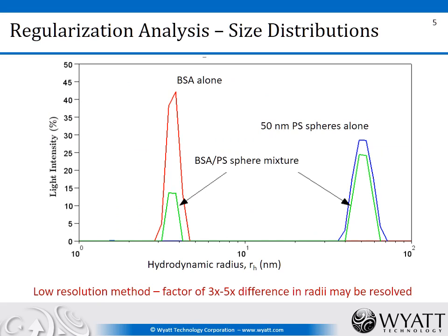Here are examples of three different measurements. Bovine serum albumin, a smaller particle, produces a single monomodal peak with an average radius of about 3.6 nanometers. A 50 nanometer polystyrene sphere produces a blue monomodal peak with an average value of 50 nanometers and some polydispersity representing the width of the peak. If we measure a mixture containing both BSA and the polystyrene spheres, which are sufficiently separated in size, we see two distributions centered around each particle, each with its own average value and width.